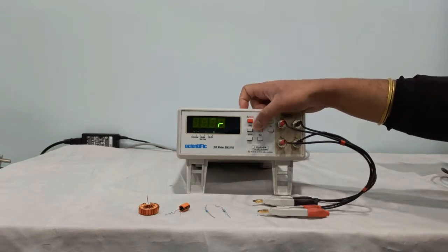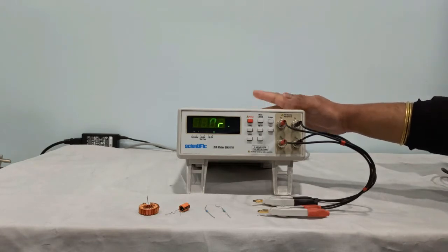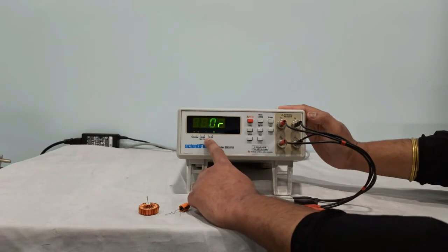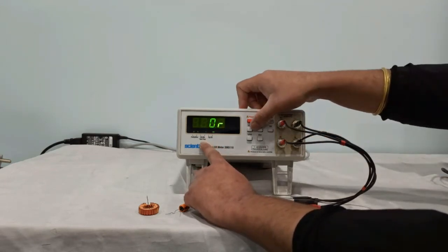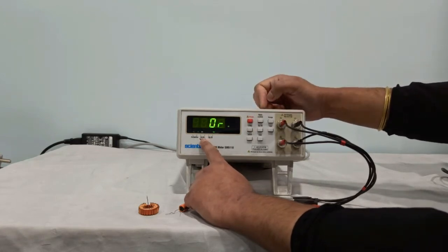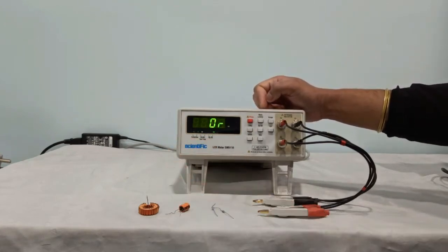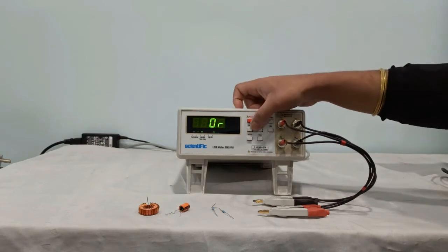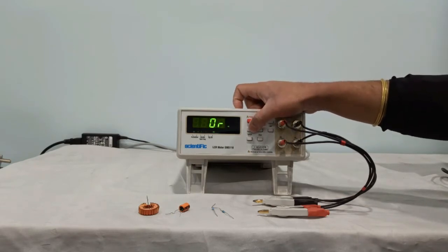Next is frequency. This instrument has two frequencies, 100 Hz and 1 kHz. Right now in the display if you see, one is displayed, so this is 1 kHz. Once you press this frequency switch, now this is 100 Hz. So you can have two test frequencies, 100 Hz and 1 kHz, and you can switch from this switch.